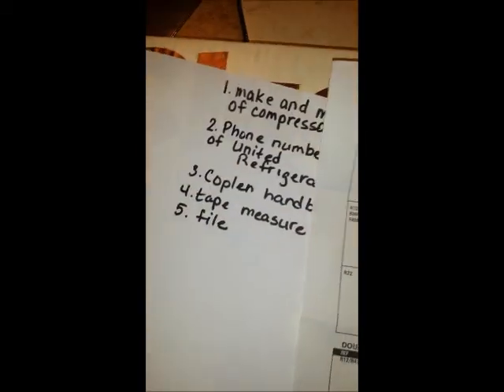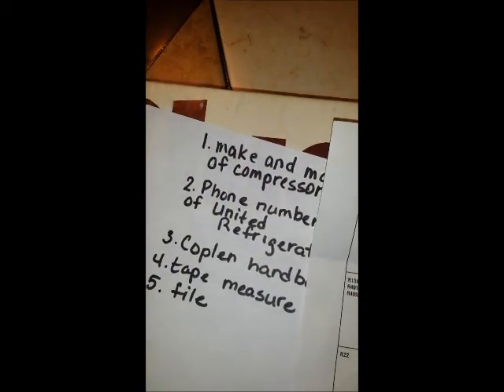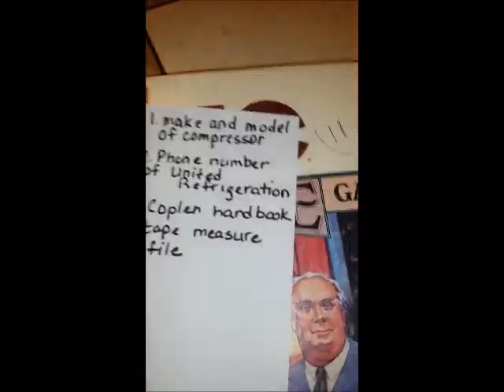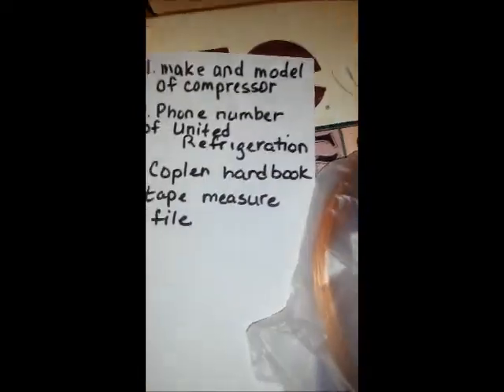So you go on here and you have number one, number two, number three, and number four and number five. We need number three and we need half horse, 52 inches long. So then you take the capillary tube out of the package. You take a tape measure. You stretch it out. You measure it 52 inches long.